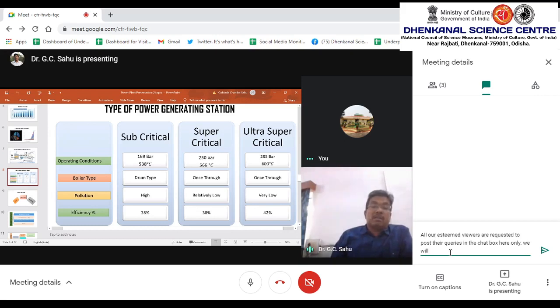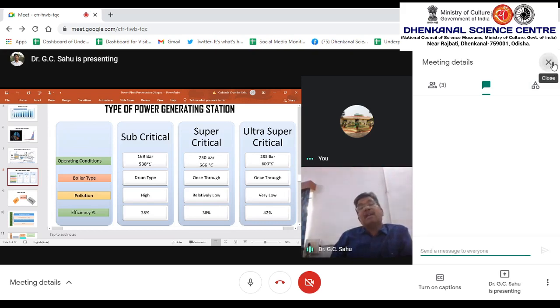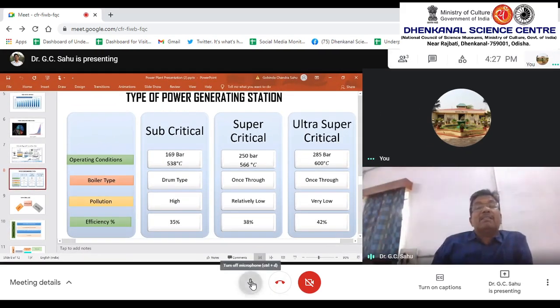If you compare the efficiency of the boiler, it is only 35% in the case of a subcritical boiler, but in a supercritical boiler it is 38%, and in an ultra supercritical boiler it is 42%. Less than 500 megawatt is subcritical, 500 and above is supercritical, and 1000 and above is called ultra supercritical. At present, there is no ultra supercritical boiler in India. The US and China have ultra supercritical boilers with 1000 megawatt generation capacity, meaning one unit's generating capacity is 1000 megawatt.